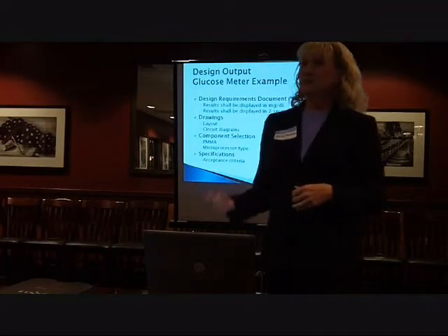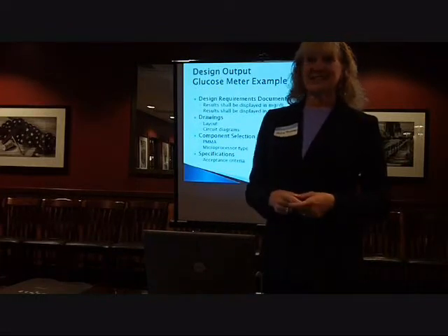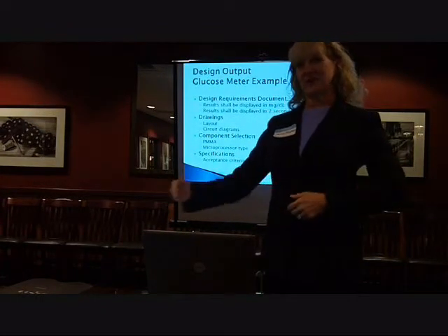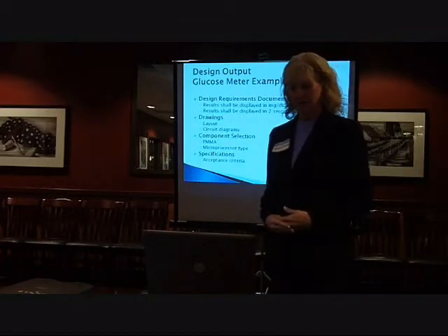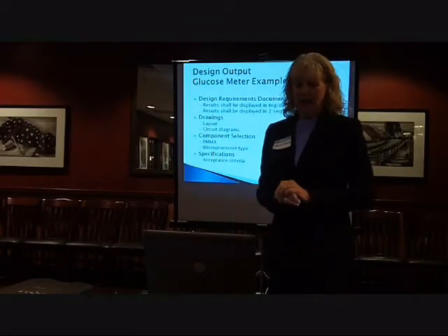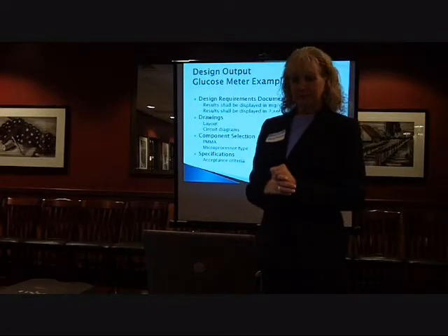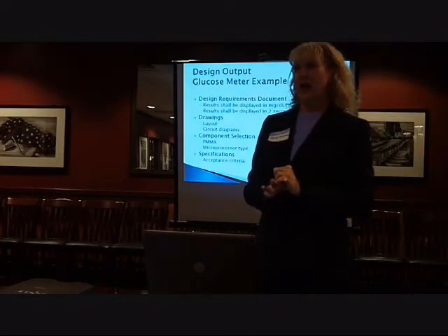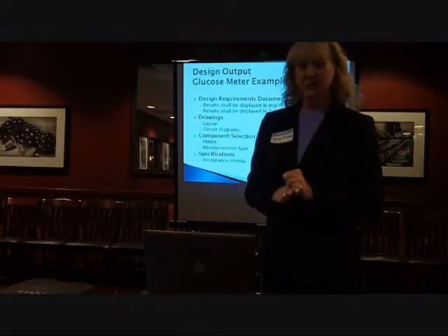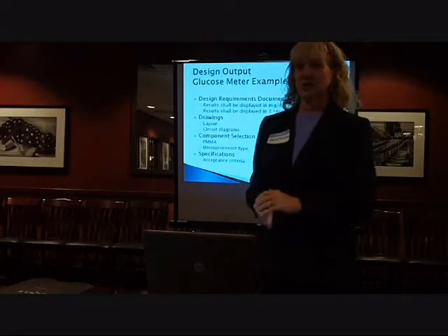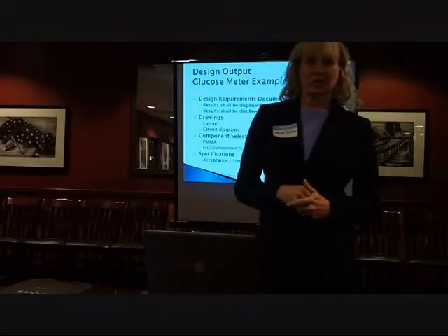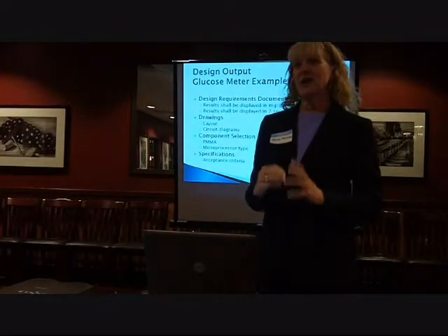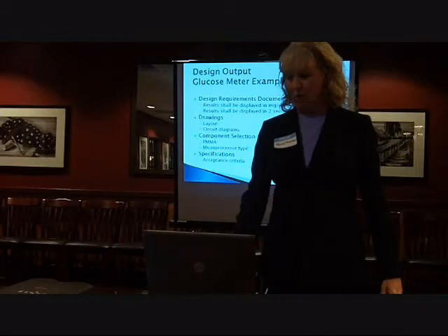And again, it's an iterative process throughout the design. So you may select something up front, and then as you go along, you may find out you need more memory, more power, you need more something there. And a very important part is that specifications are the outputs, and those need to already have acceptance criteria at this stage. It could change. That's okay. But you need to have a target out there, something you start working with.